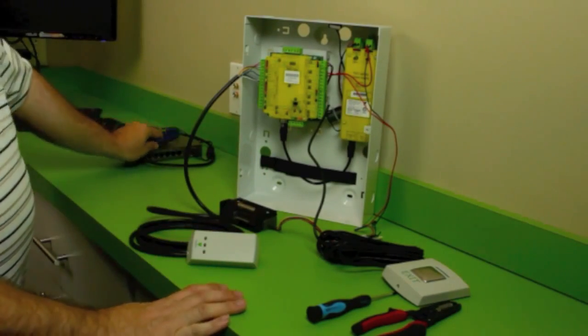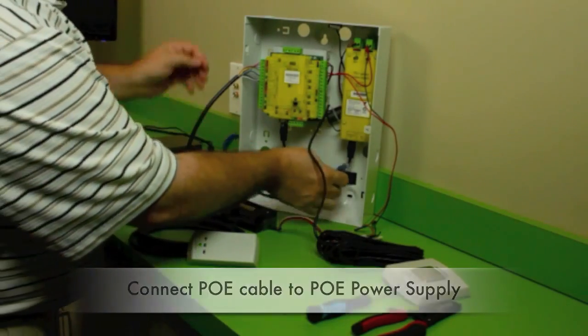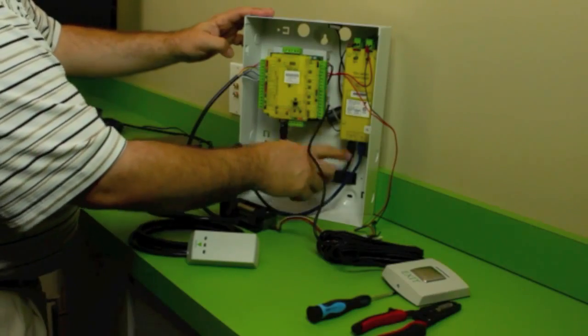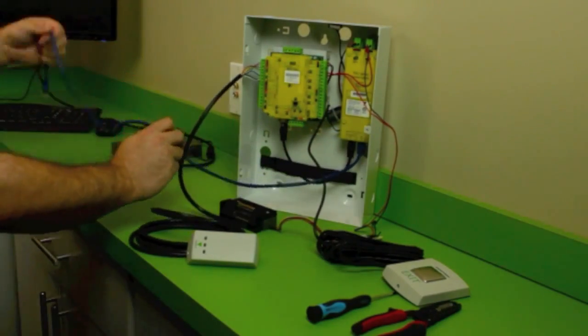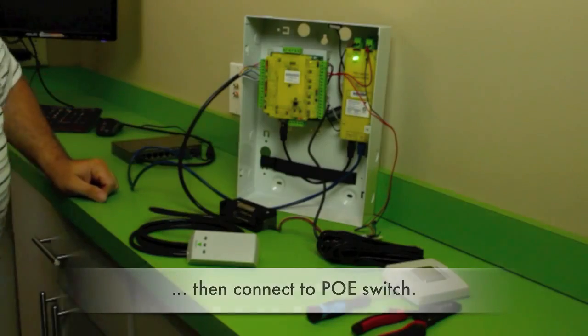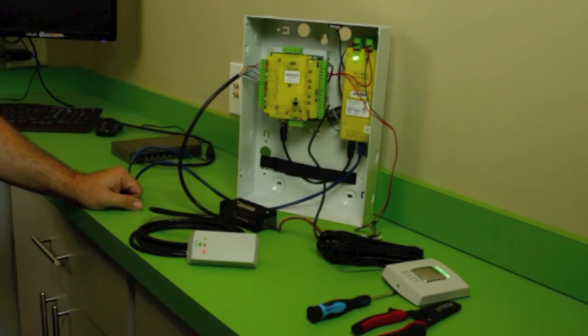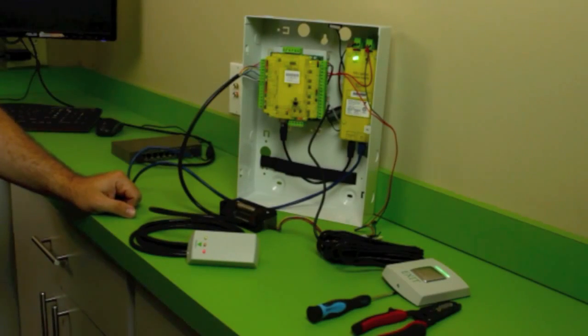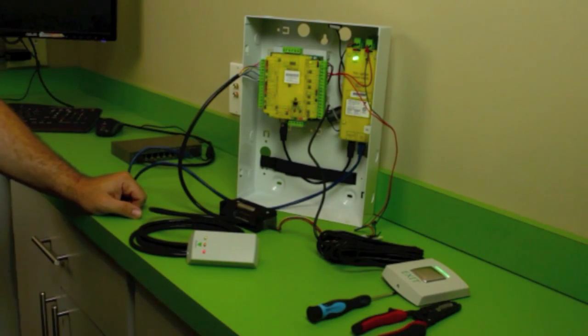Last thing you need to do now, you take your cable for your PoE. It goes right in the bottom where it says PoE in. It comes from the factory already with a jumper cable from Ethernet out to the Net2 Plus. And then you would plug your other end into your PoE switch. With the PoE, once it's plugged in, everything will power up. And you're off and running and ready to install it and detect it into your computer on the software where it's already pre-installed.